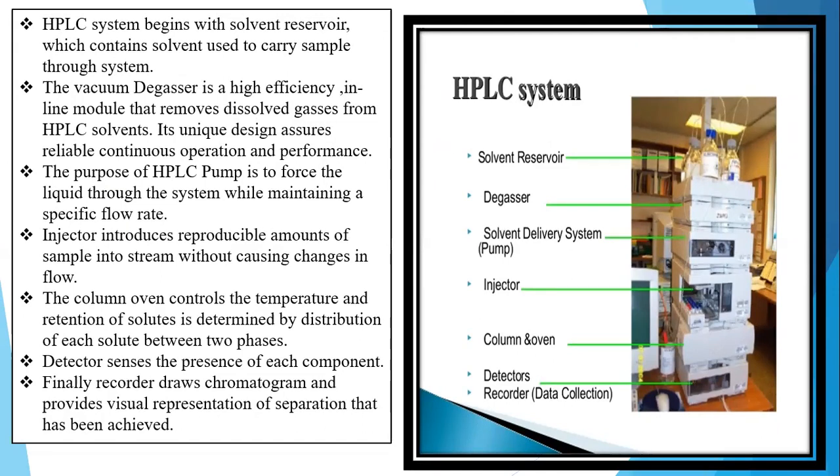Then comes the solvent delivery system, which is also known as the pump. The purpose of the HPLC pump is to force the liquid through the system while maintaining a specific flow rate. Injector: the injector introduces reproducible amounts of sample into the stream without causing changes in flow.